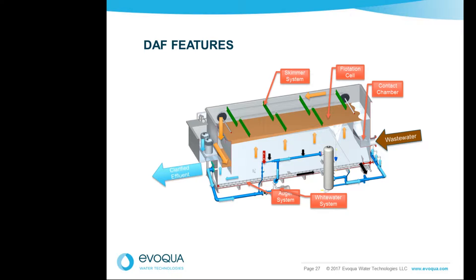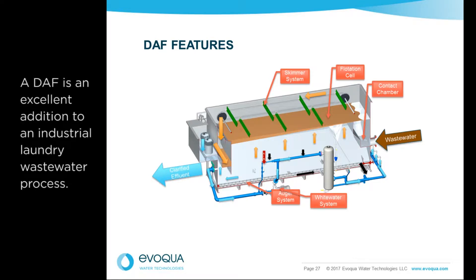DAF systems come in a variety of shapes and sizes — they can be circular or rectangular, and shallow or deep. Some systems have plate packs, some do not. Regardless, they all possess the same basic features. First, there is a contact chamber, which is where the influent comes in with the contaminant particles and makes contact with the fine air bubbles being introduced. That is where the majority of attachment takes place between the particle and the air bubble.